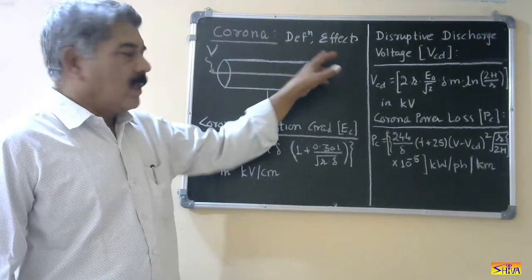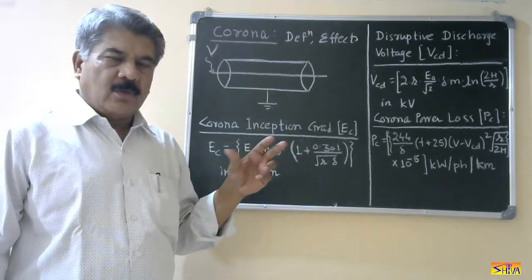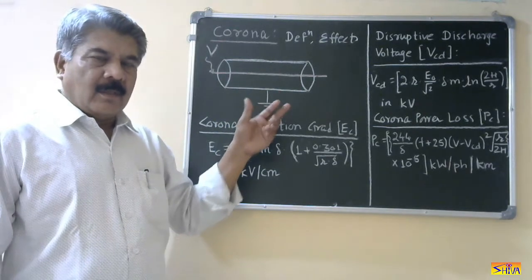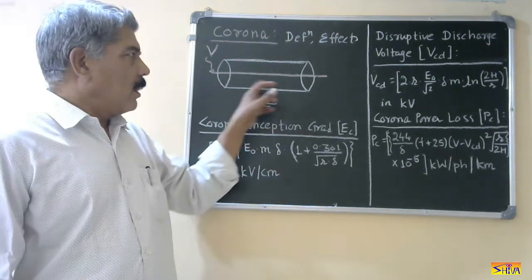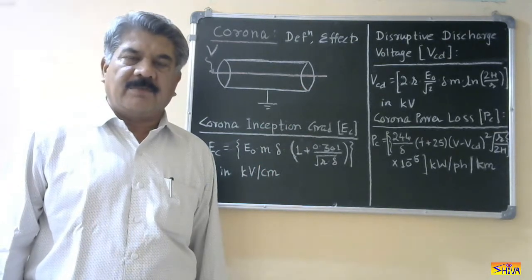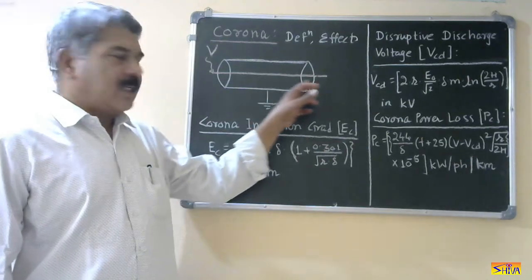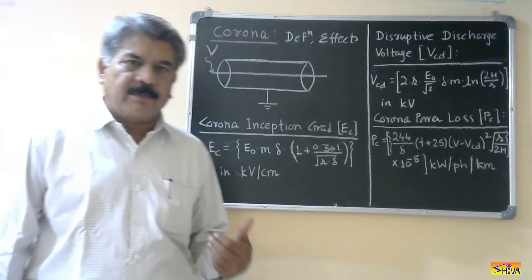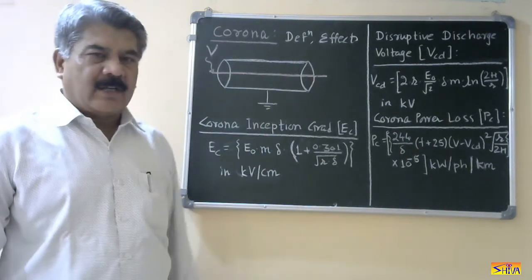Now, let us see what are the effects of corona. The first effect is that the air is ionized — air molecules break into positive ions and electrons, and they are in motion. They require some energy to keep themselves in motion; that energy they draw from the conductor and the power supply. So there is active power loss. This effect is very prominent in case of EHV lines, because in EHV lines the voltage gradient on the surface of the conductor is very high and corona power loss is very high. That is one of the factors considered while designing transmission lines for EHV. So the first effect is active power loss.